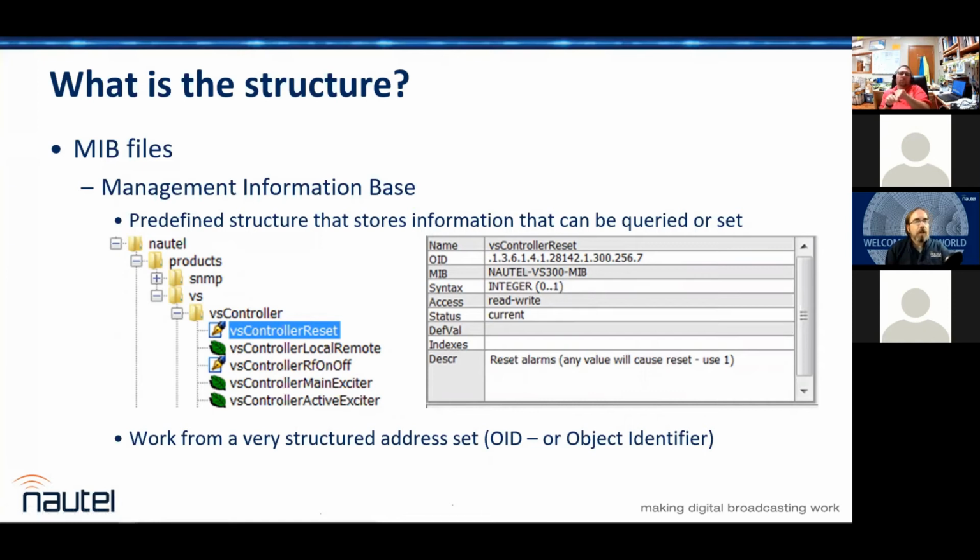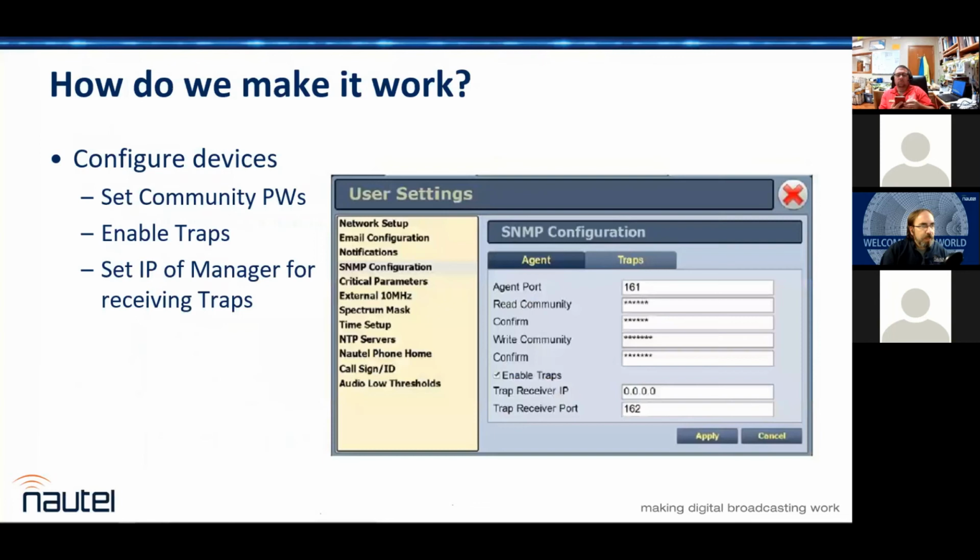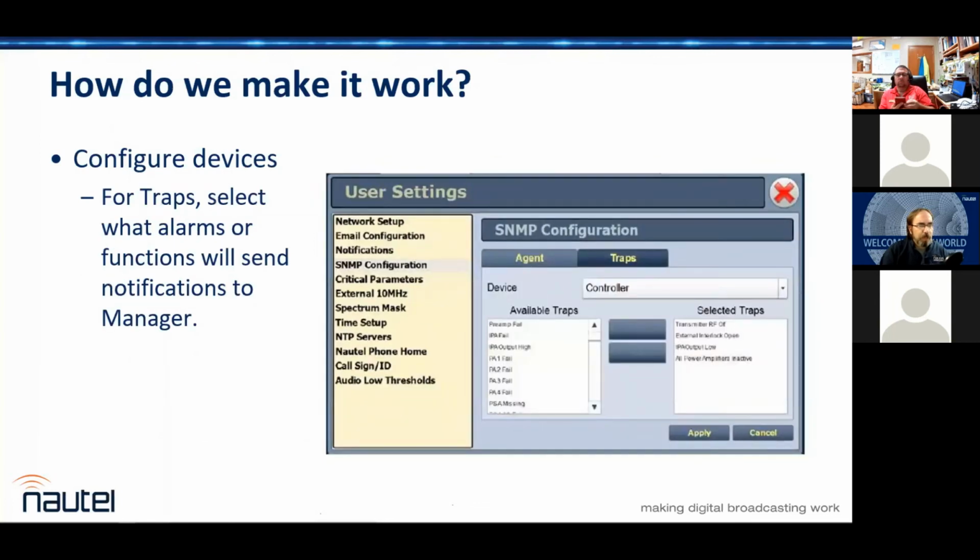But on anything like that, when you look at it with something like the iReasoning browser, it should give you the range of parameters for that particular OID. So yeah, it could be 0, 1. We monitor meter readings to the milliwatt or millivolt, so that very much would be an analog reading as far as the scale that it reads. So yes, there will be multiple states in some cases. That makes sense? Or did I just make it more confusing?